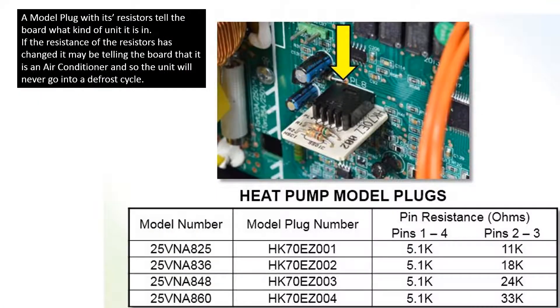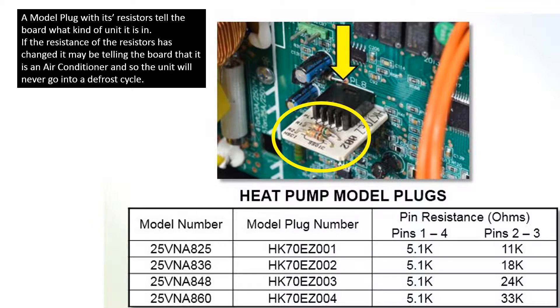Many manufacturers use a model plug with resistors to tell the board what kind of unit it is operating. If the resistance of these resistors has changed, it may tell the board that it is an air conditioner, so the unit will never go into a defrost cycle. A few years ago, a technician had changed the board, changed the defrost sensor, and changed everything he knew to do, yet the unit would still not defrost. We found that the resistors on the model plug were out of range, telling the board it was an air conditioner rather than a heat pump. Once we installed the proper resistors on the model plug, the unit went immediately into defrost.